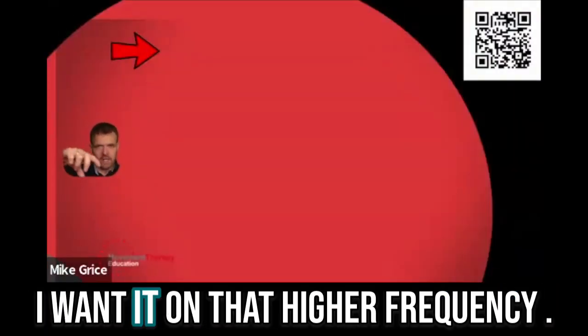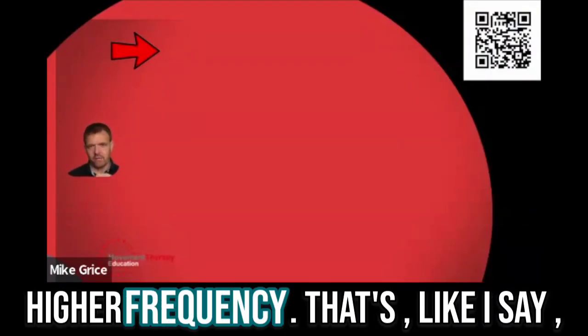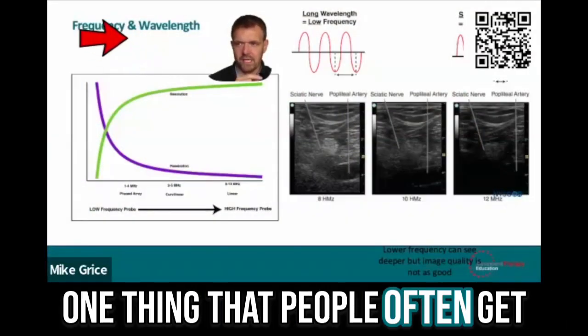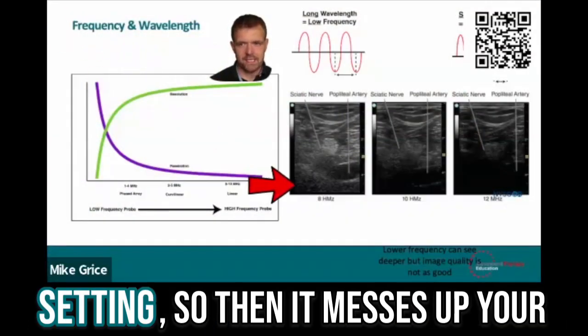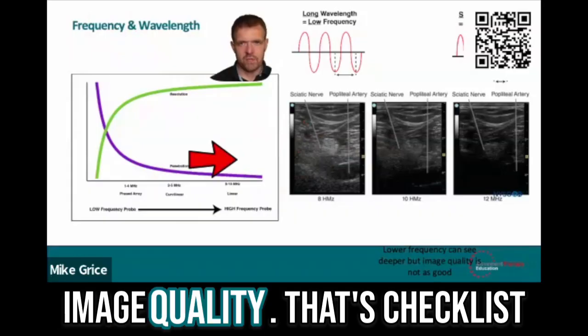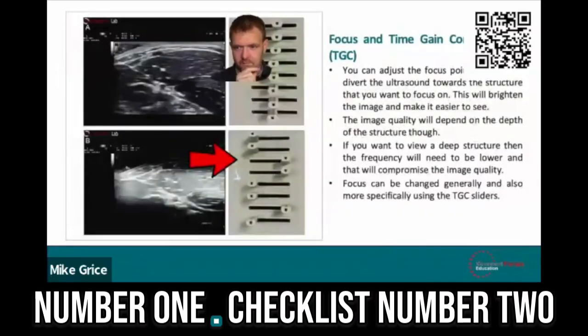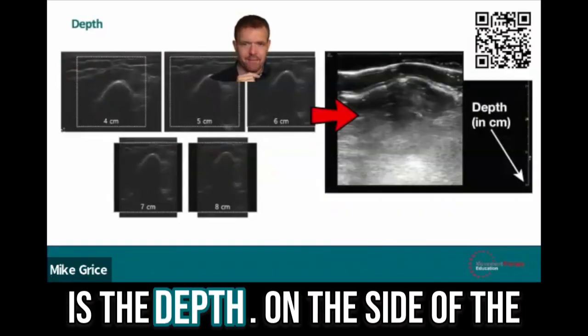If I'm scanning something superficial, I want it on that higher frequency. Achilles, definitely want it on that higher frequency. That's, like I say, one thing that people often get wrong. The frequency is the wrong setting, so then it messes up your image quality. That's checklist number one. Checklist number two is the depth.